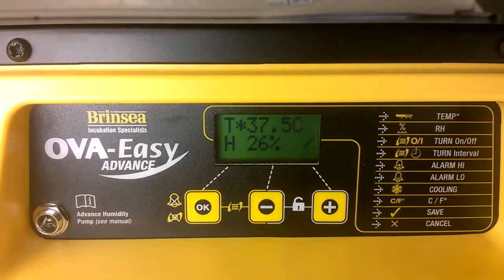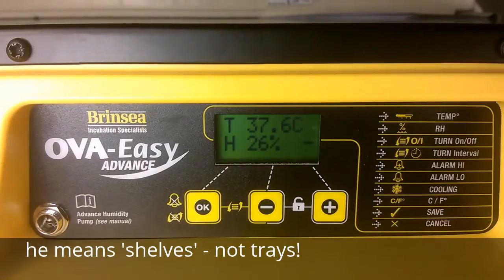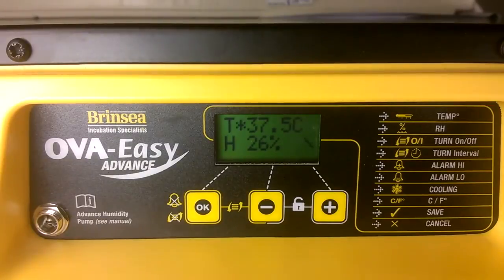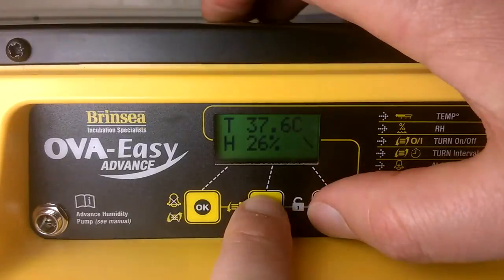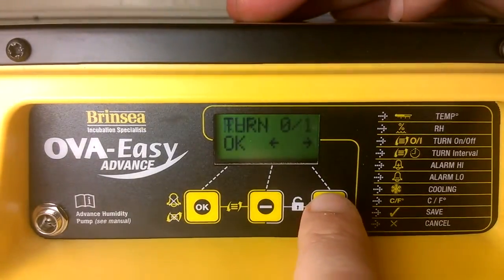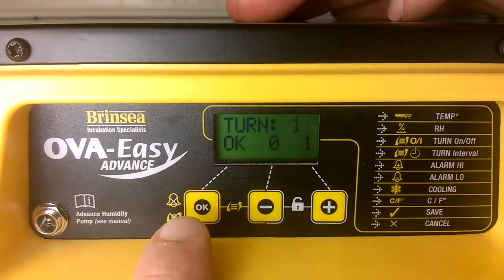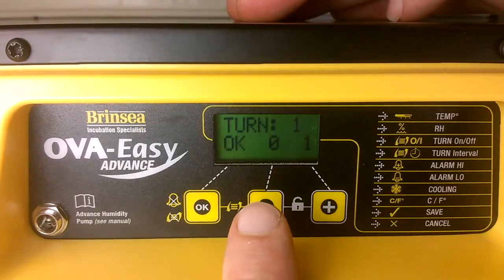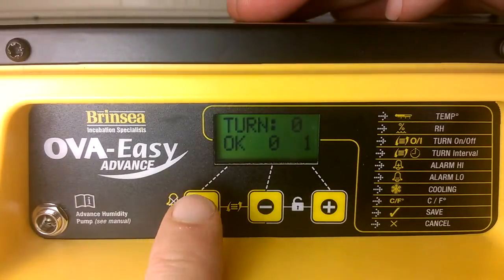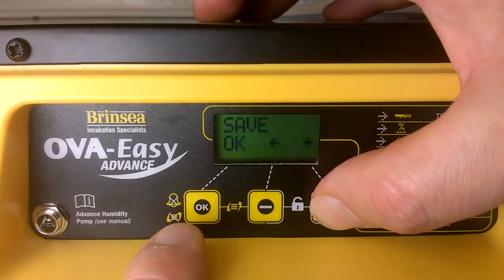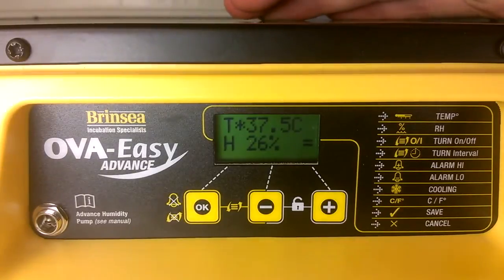What we need to do is to ensure that the trays are out of the machine, that we have leveled the shelves out using the menu, the digital menu on the machine, and that the water tray remains fitted in the machine. So one of the things we need to do first of all is to instigate a leveling of the trays in the machine. Now the easiest way to do that to avoid problems is to go into the menu, the minus and the plus button together, to go down as far as the turning, to press OK once you get to turning to enter into that menu, and to turn the turning so that it's off. In other words, it's on 0. At the moment it's on 1, so let's move it to 0. Let's press OK, and then let's carry on through the menu until we get to save and press OK.